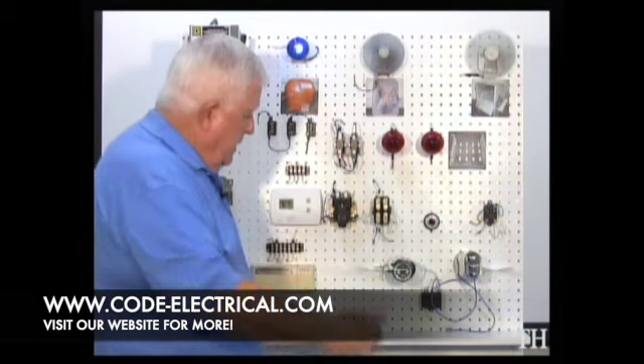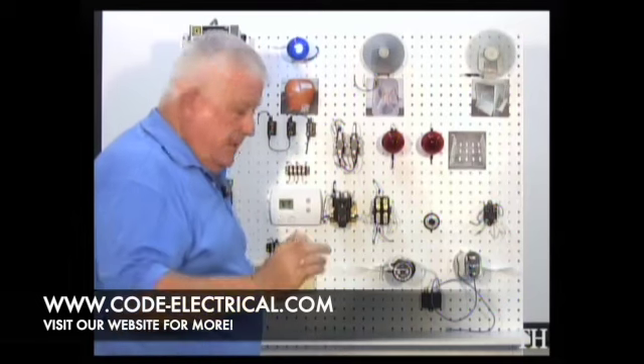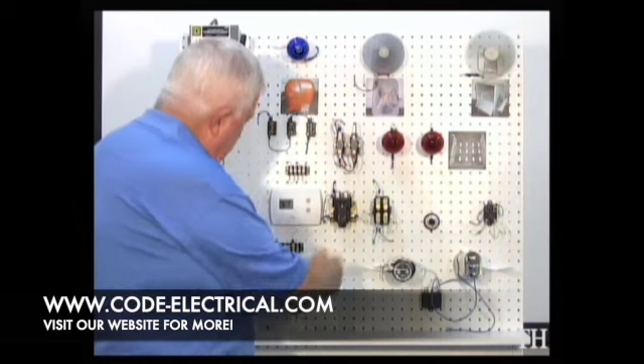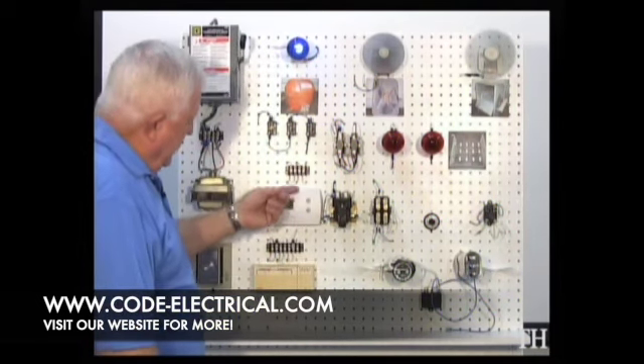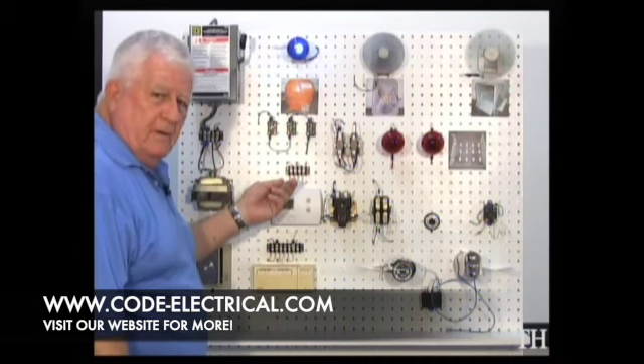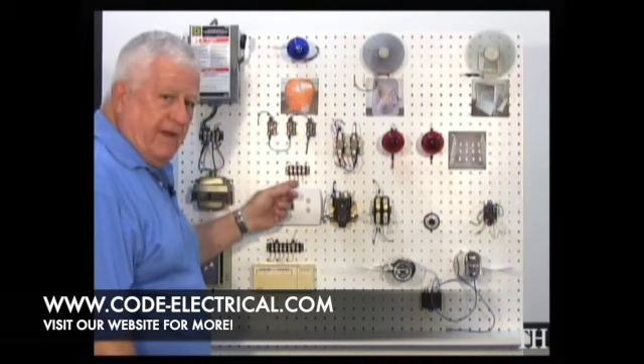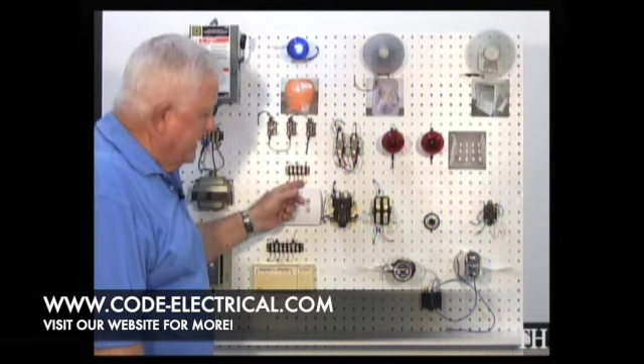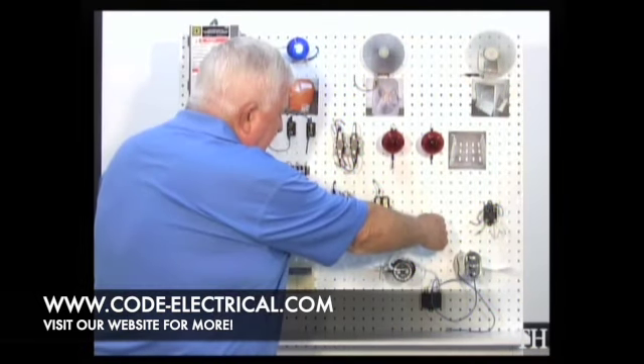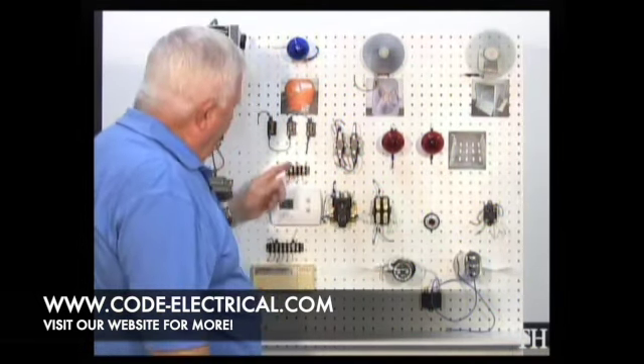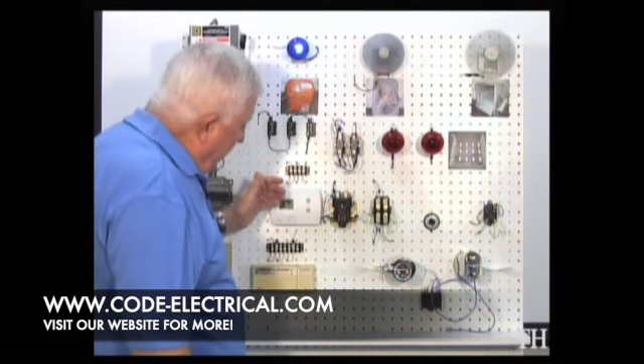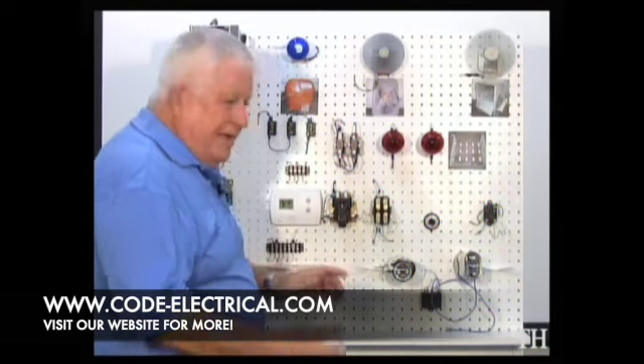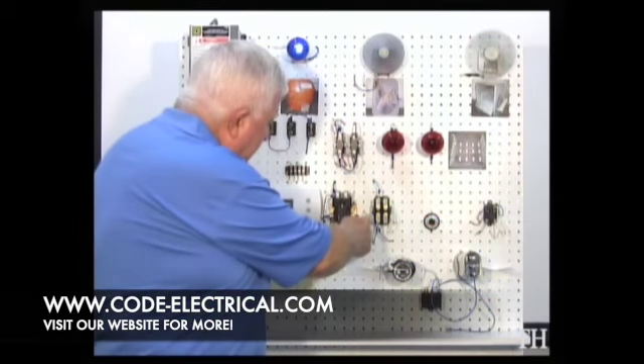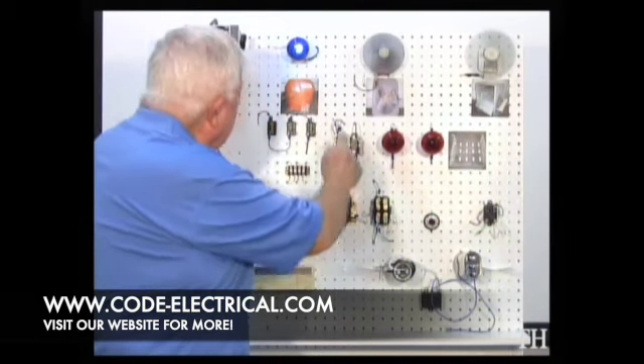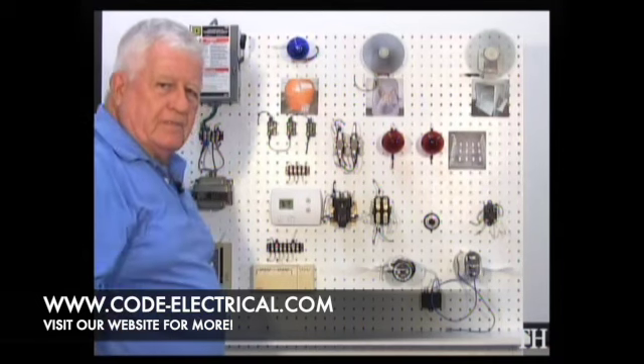you through it, the control relay got the signal. See the yellow? That's a yellow off the thermostat. Yellow's cool, remember? Red's power, green's fan, white's heat. White is what comes over to this guy and this guy. But right now I'm talking about air conditioning, which is yellow. I fire the control relay. When it picks up, guess what? It energizes the contactor to start the compressor.